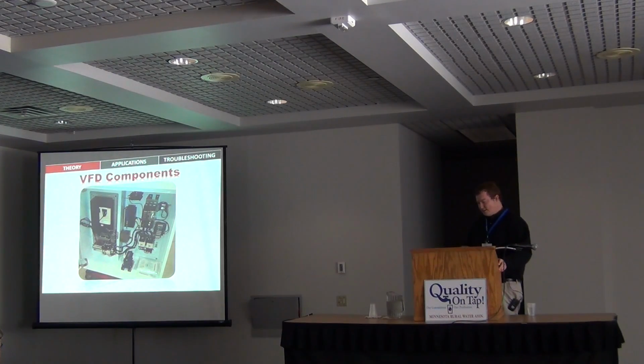I wanted to show this slide. I took this photo yesterday on the showroom floor. It was a little VFD in an enclosure from Schneider Electric, so I wanted to go through the components, if you can see them way in the back. On the right, there's a main circuit breaker within this enclosure. From there, it looks like, down here, they must have a bypass contactor, so if the VFD failed for some reason, they could run this across the line.